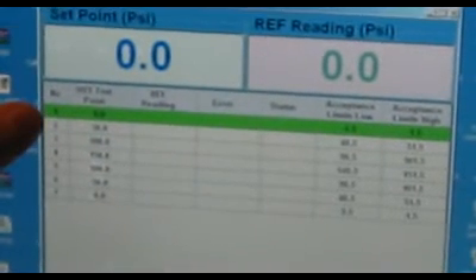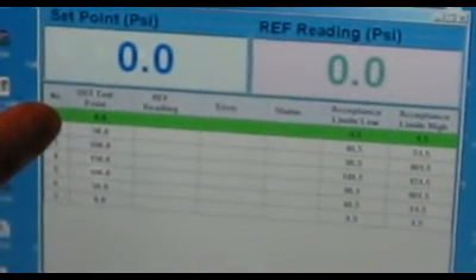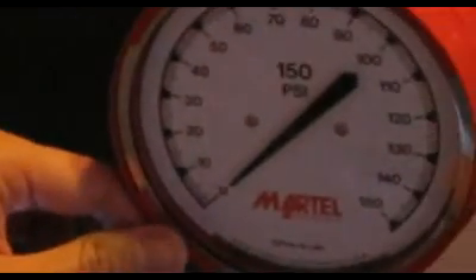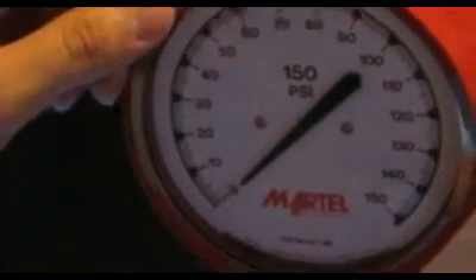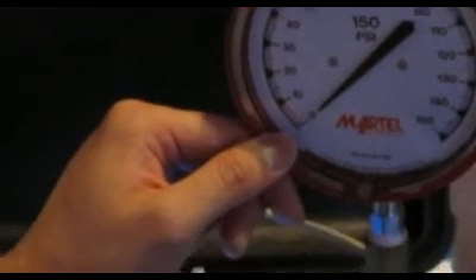Now we start with the first calibration point of 0 psi. We will focus on the analog gauge: 0, 50, 100 and 150. At each point we will simply tap enter. Now 0 psi.